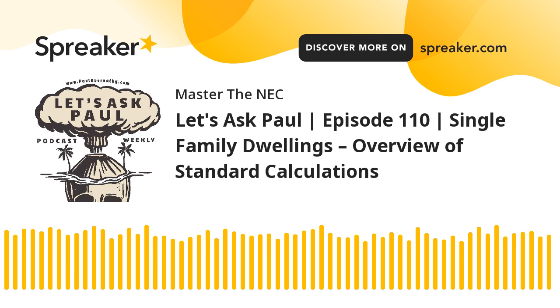So I did my load calc. It was 193 amps. I'm just using numbers here. So then I say, okay, what is the size of this service if I have a calculated load in amps of 193? All right, so you're going to go to 240.6(A), and you're going to look at your options. These are standard size overcurrent protection. And I'm looking, and I'm seeing, okay, I don't have anything for 193, but I have something for 200. So I'm going to be able to install it on 200 as long as we don't exceed 800 amps.